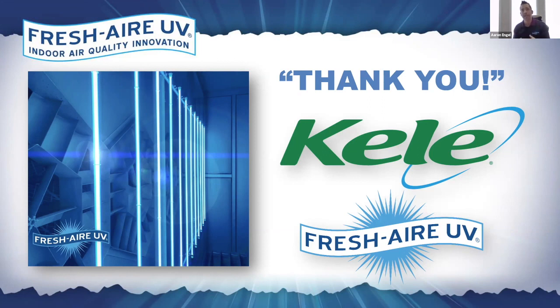But as far as data to show that it's effective at neutralizing viruses and bacteria in how it's designed to work, it's fine to take an ionizer, put it into a small 1 cubic volume of air and run it for 24 hours. But it's another thing taking that same unit, putting it in the ductwork with moving air in a 20,000 cubic feet facility. It just doesn't translate. UV light has thousands and thousands of peer-reviewed research data to show that it works as designed. And I would complement UV with bipolar in order to improve the filtration side of what the facility wants to do.